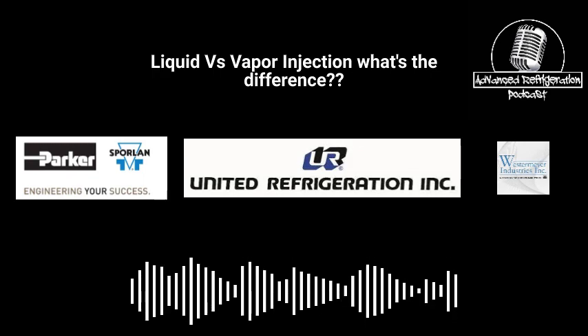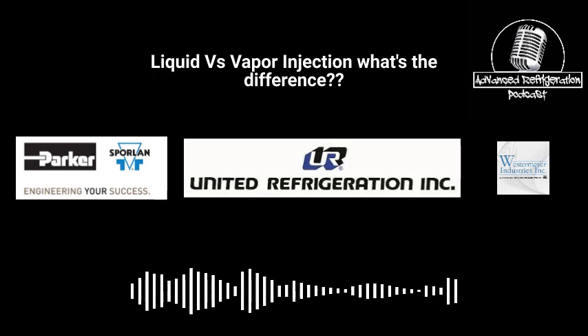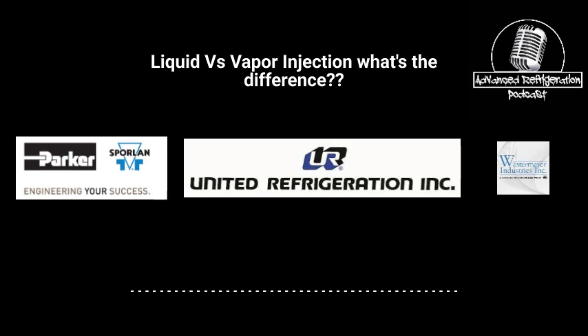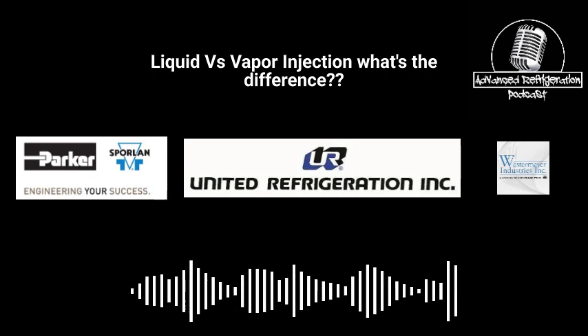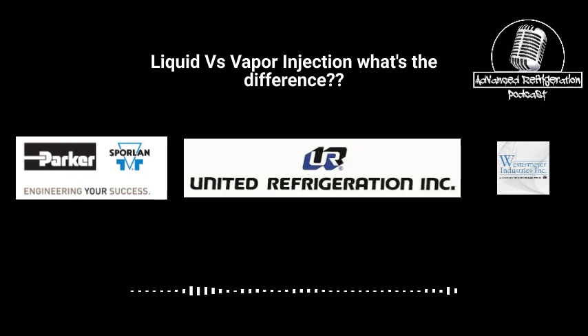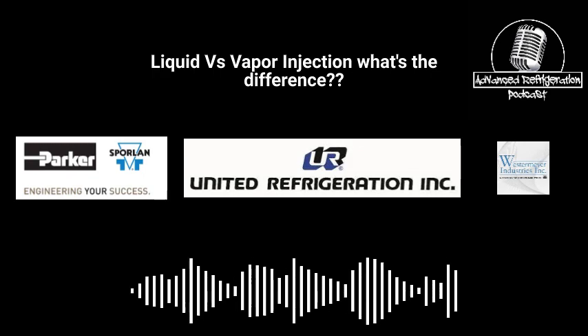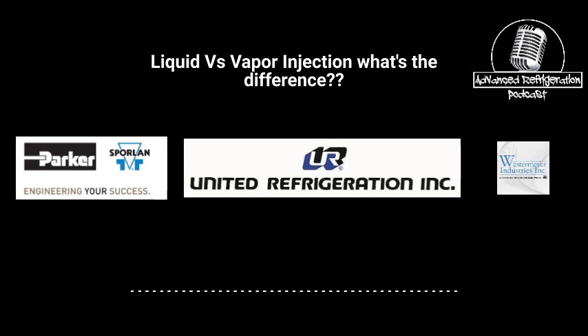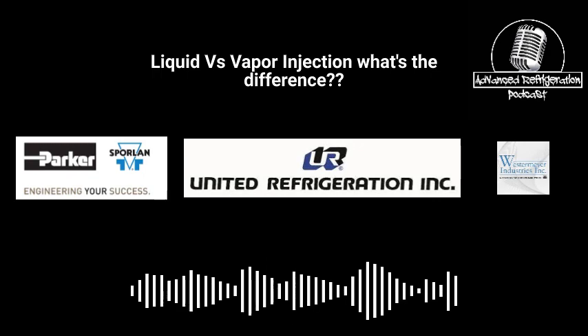And on those compound compressors, not only are we utilizing vapor injection, but we are also utilizing the liquid injection as well. Yeah, which I honestly think all compressors should have both and variation for both. I think they should all have both because A, if that subcooler shuts down or something happens to it, you still have that liquid injection. And then B, it's a temperature protection for the compressor.